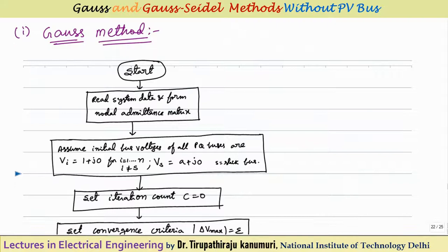For the Gauss method, the first step is to read the system data and form the nodal admittance matrix. Once formed, we assume initial bus voltages for all P-Q buses as 1+j0 (i.e., 1∠0°) for i = 1 to N except the slack bus. For the slack bus, the voltage is already specified as A+j0 = A∠0°.